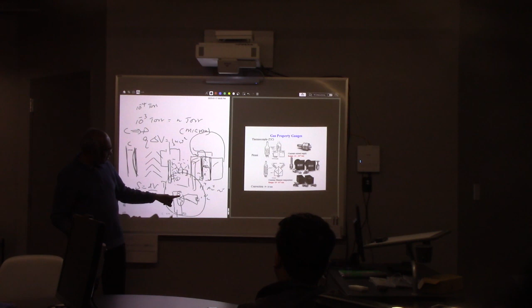If I pump this one down, you have fewer gas molecules, so the temperature won't drop as much, because less heat is given away. If you completely pump it down, you have only a few molecules, so the temperature will be even higher. By measuring this temperature, you can directly get the pressure. That's basically what they do.